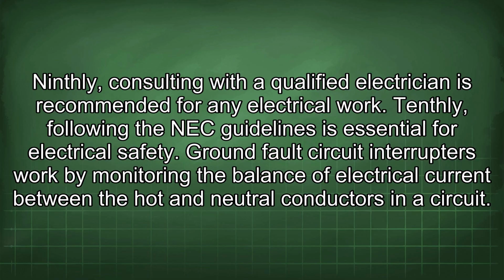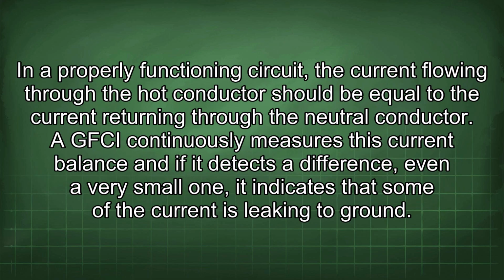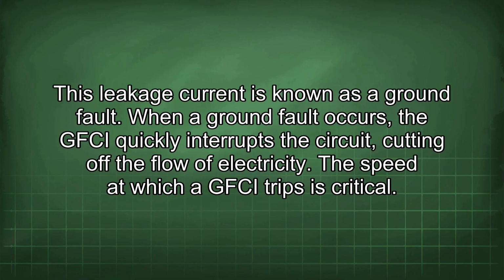Ground fault circuit interrupters work by monitoring the balance of electrical current between the hot and neutral conductors in a circuit. In a properly functioning circuit, the current flowing through the hot conductor should be equal to the current returning through the neutral conductor. A GFCI continuously measures this current balance, and if it detects a difference, even a very small one, it indicates that some of the current is leaking to ground.